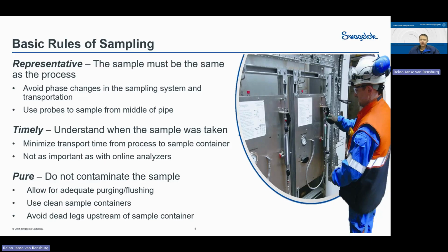For instance, if you sample from a tank and you don't have a free-flowing system, and your sample point is, let's say, 20 meters away, and you only sample 100 or 300 mils at a time, you could be sampling things that happened days ago. So it would not really give you a representative reading of what's in that tank at that point. It could be material from days ago.